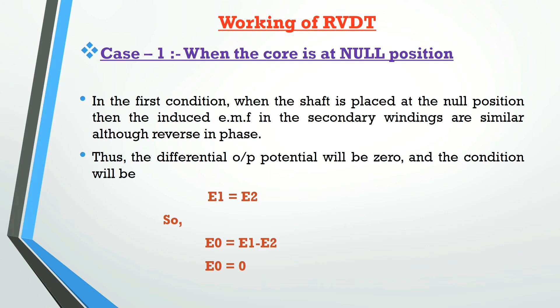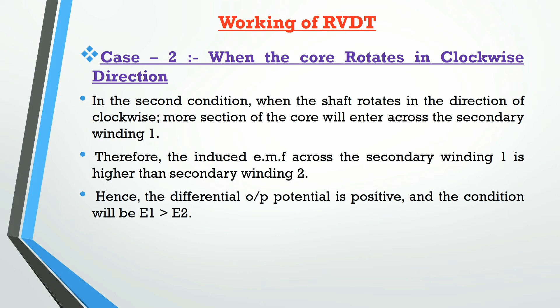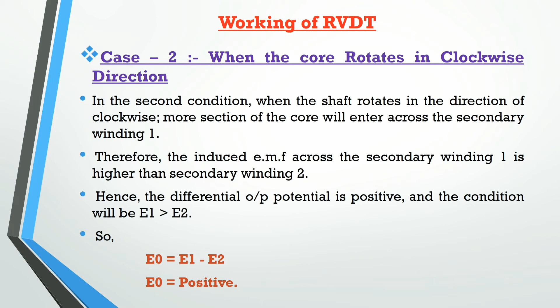Now let us see case number 2, when the core rotates in the clockwise direction. In the second condition, when the shaft rotates clockwise, more of the core will enter across secondary winding 1. Therefore the induced EMF across secondary winding 1 is higher than across secondary winding 2. Hence the differential output potential is positive and the condition will be ES1 greater than ES2. So E0 is equal to E1 minus E2. Here E1 is higher than E2, so E0 is positive. So when the core rotates in the clockwise direction, the output of the RVDT is positive.